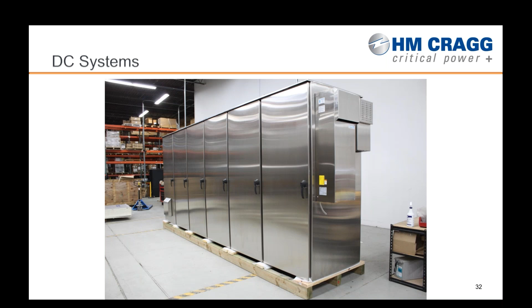And then in this design, bays 2 through 6 are completely sealed, HVAC controlled, always at 77 degrees. And this one was specifically a wet cell battery string on the inside. So we had provisions for the racking to be mounted. We actually mounted the racking. We did not ship with the batteries installed, as you can imagine. But like I said, 77 degrees is the temperature in the battery bay all the time. We have hydrogen sensing and hydrogen exhaust in these DC systems.